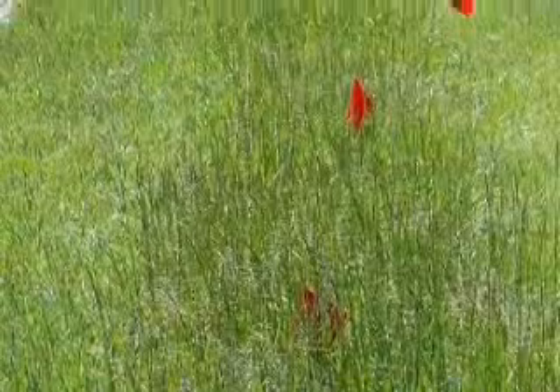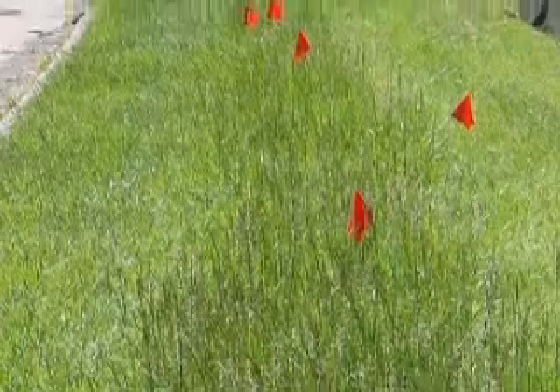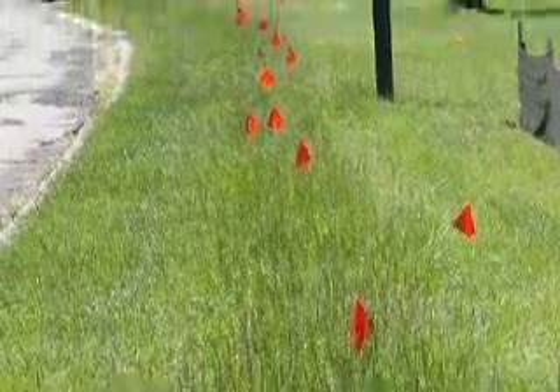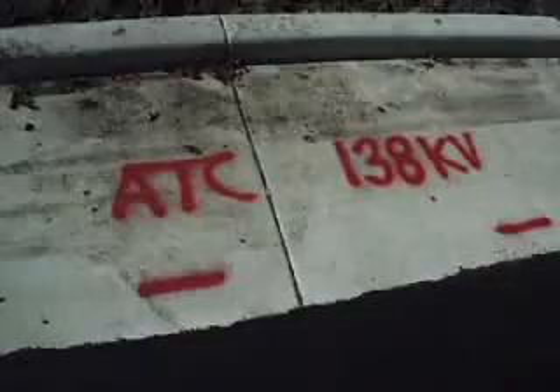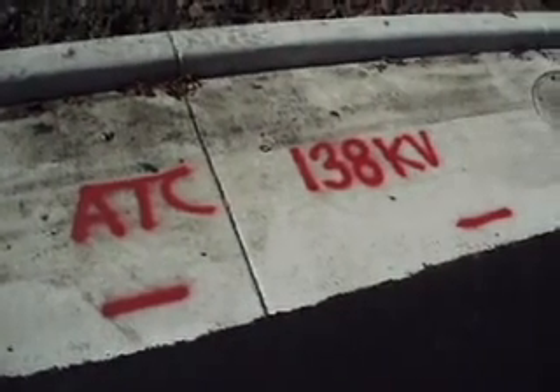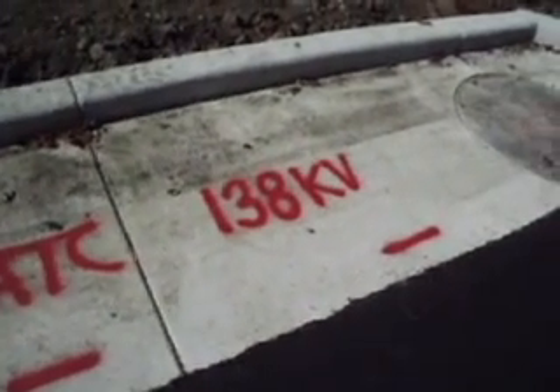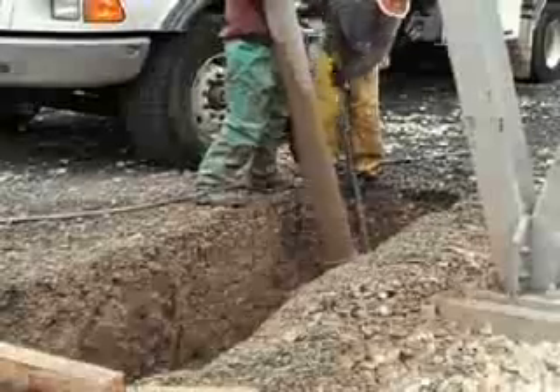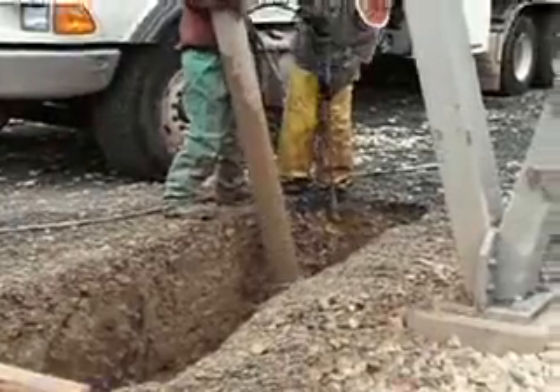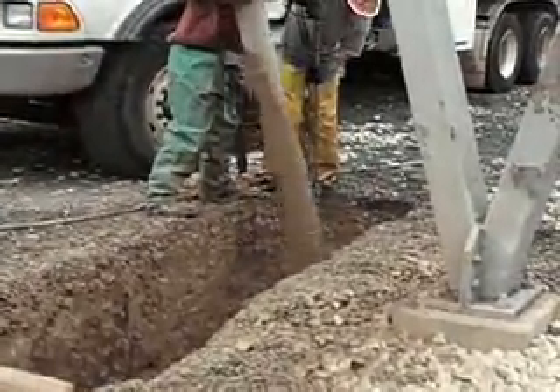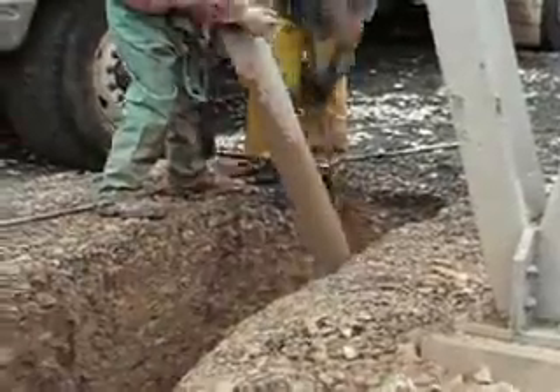Before you can safely work near an underground transmission line, you must first locate the line and verify its depth. Flags and locator marks indicate the direction the cable is running, but not how deep it is buried. The only way to be sure of the cable depth is to carefully expose it. Prior to crossing or paralleling any ATC transmission line with directional drilling construction methods, the line must be exposed by hand digging or vacuum excavation.